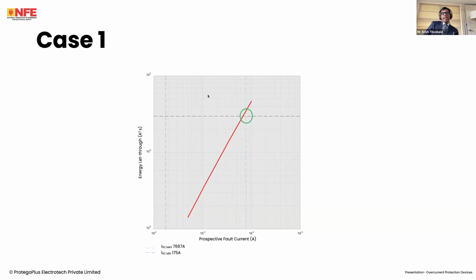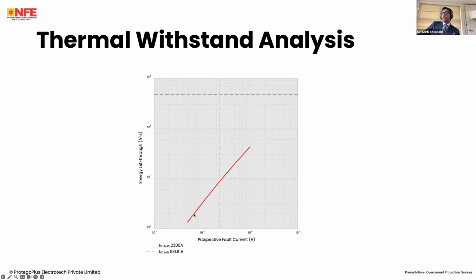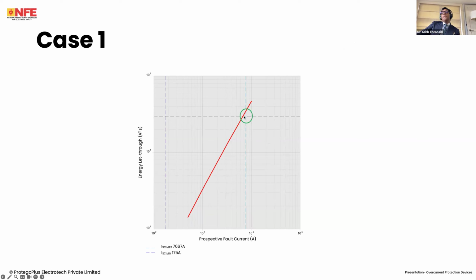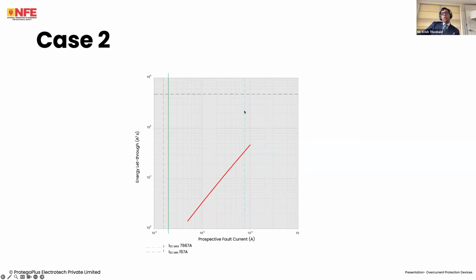Where does it go wrong? Case number one: this graph, this red line, which is always provided by the manufacturer of the OCPD, goes above the thermal withstand. Imagine, in a separate case, the maximum short circuit current is 7,667 amps. Over this certain value, I squared T exceeds K squared S squared. So the cable will be damaged for short circuit currents at this point. Option two is that the device is just not going to disconnect, and the amount of let-through energy is so massive that the cable is not protected for short circuit currents below this, because the device will simply not disconnect.